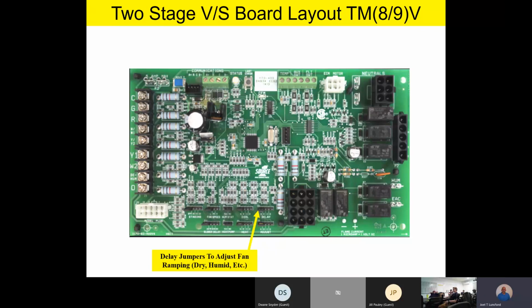So the idea is this delay profile gives you the option, based on your local geography, to really have a cooling on delay profile to help control moisture or to have added capacity for the unit and so on. And again, this is very well explained in the install or the technical information that comes with the equipment, but we just wanted to review that real quick for you, that you have some really nice airflow on delay and cooling on delay functions by way of the delay jumper.